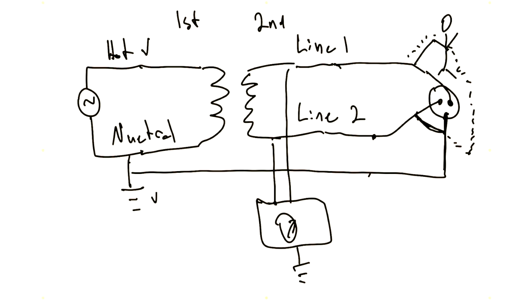So that's the key. The key about the isolated system is it gives you one additional fault that can always occur. You can always be in a single-fault condition and be safe and get a warning. By safe, I mean you're not getting shocked at that moment. However, as soon as there's two fault conditions, now there is imminent danger. You will be shocked if you are in the path of the circuit. Of course, there's always the potential that you're not in the path, but something else is in the path, such as a medical device or some other piece of equipment.